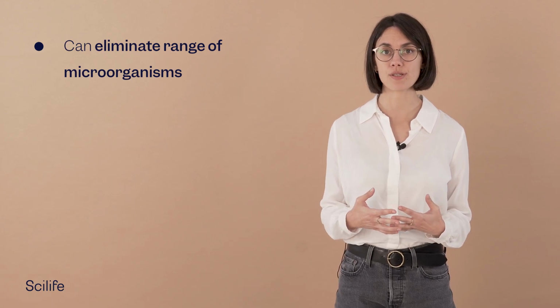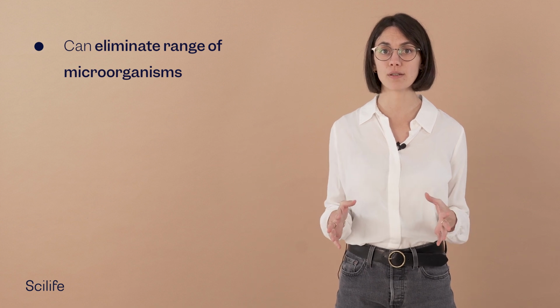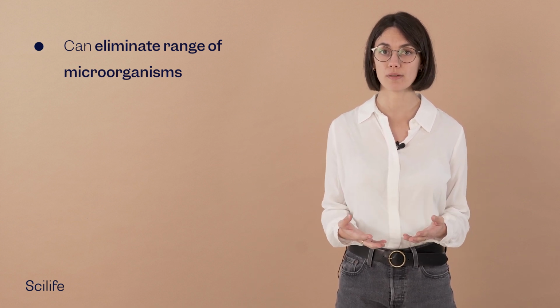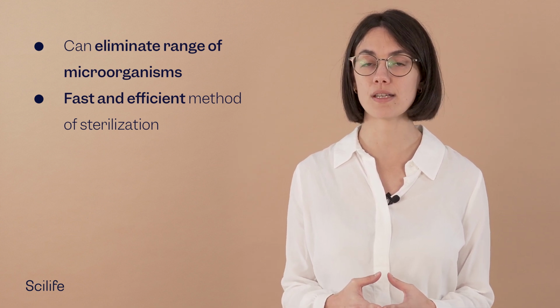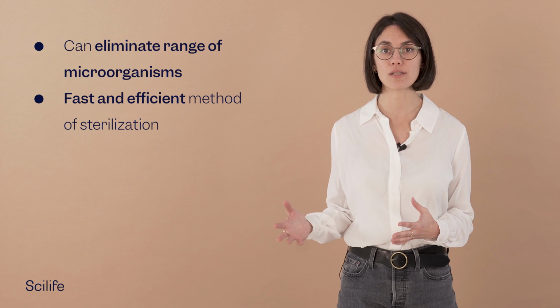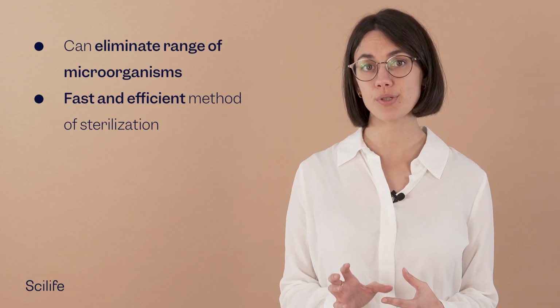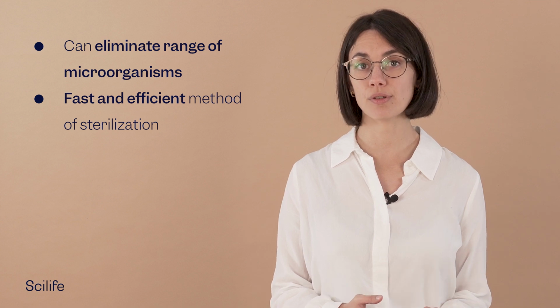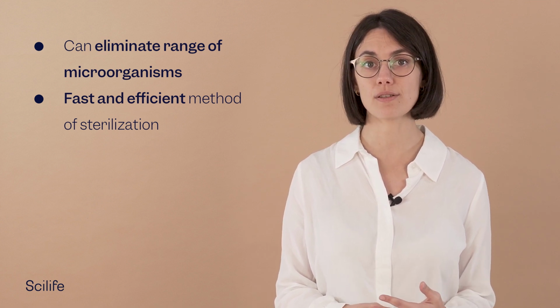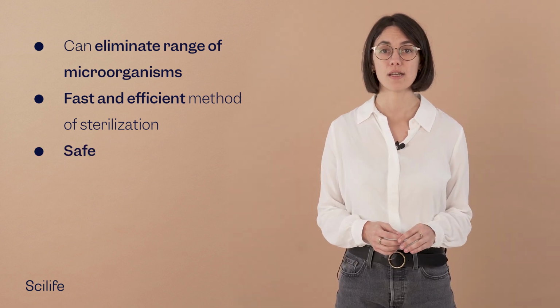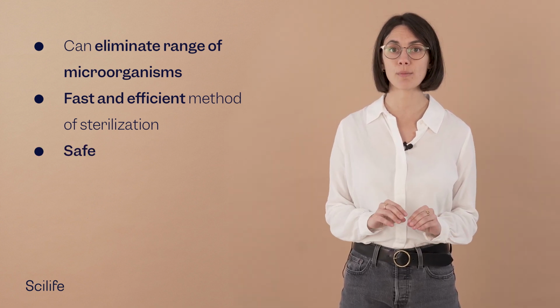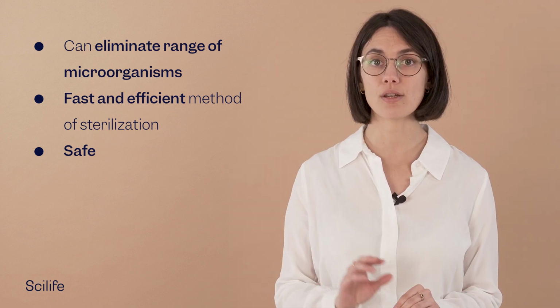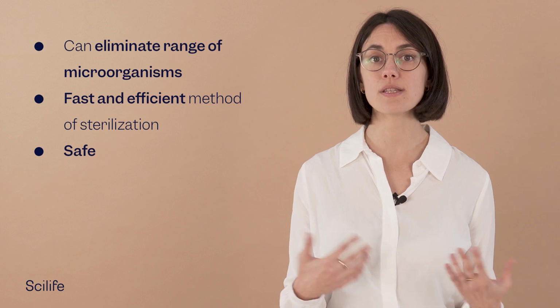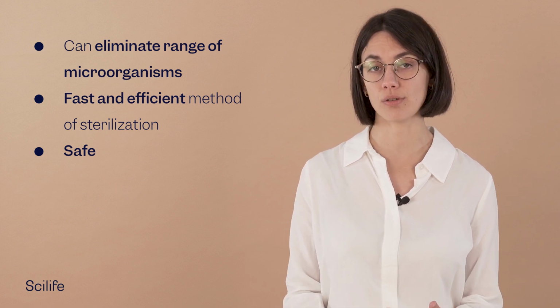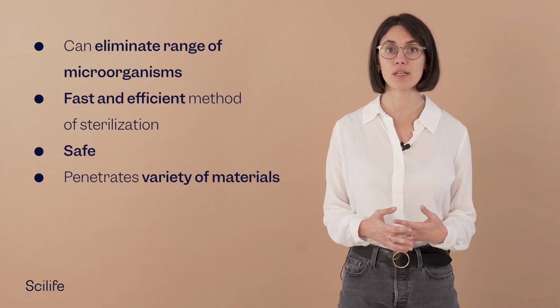What are the benefits of electron beam radiation? Well, it's an effective sterilization process that can eliminate a wide range of microorganisms, including bacteria, viruses, and spores. Plus, it is a fast and efficient method of sterilization. The process is able to sterilize large quantities of products in a relatively short amount of time. The speed protects the product's material properties, prevents polymer degradation, and causes no damage to sterile seals on product packaging. It's a safe process. It does not use chemicals, so there is no risk of chemical residue remaining on the product. It reduces the oxidative damage to the product irradiated and avoids a color change in polymers present in packaging or medical devices. And it can penetrate a variety of materials, including foils.